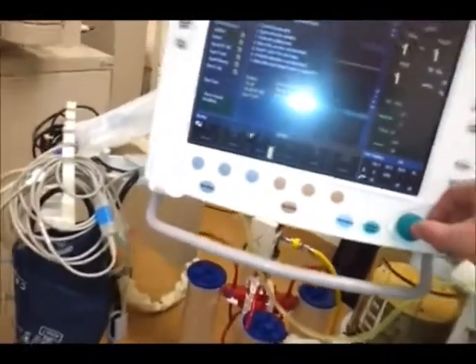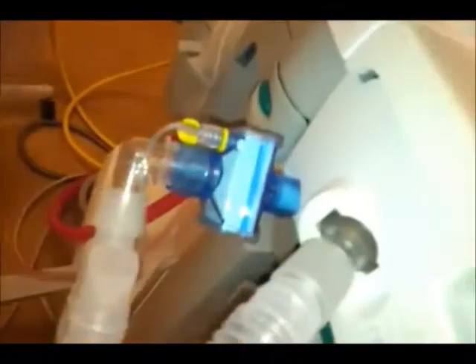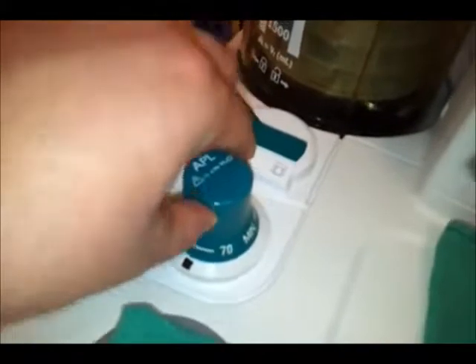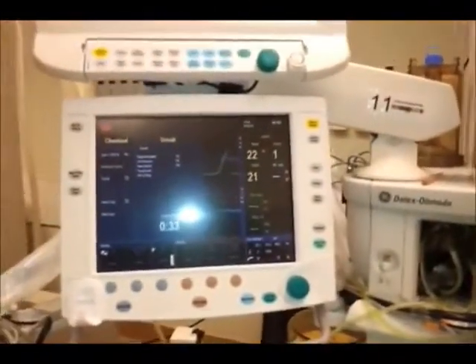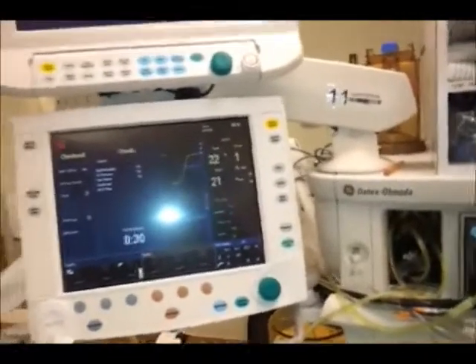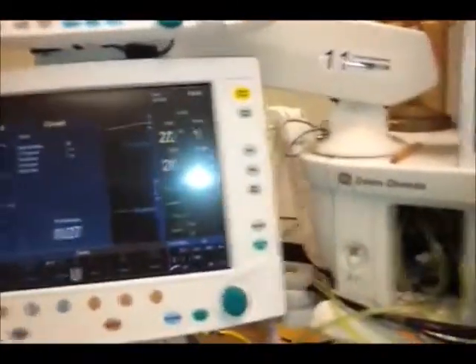Circuit test, so you go down to circuit, hit enter. Okay, so you want to occlude the patient Y, which is still occluded down there. So you want it switched to bag, and set the ACGO switch to circle, which it's still set at circle, so point it up. And then you want your APL valve between 30 and 70. You should hear the little click when it goes above 30. So, that's all you need for this one. So, 34 seconds. I guess we'll just wait for this one to finish. Okay, so we're going to look at the sheet for a second.